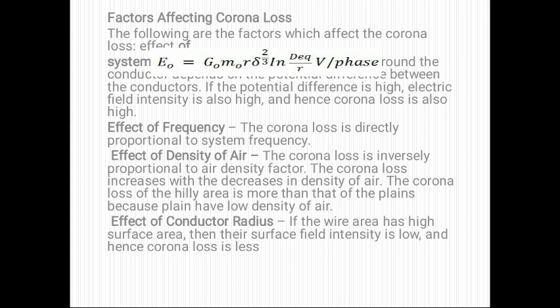Now, factors affecting corona loss: system voltage, effect of frequency, effect of density of air, effect of conductor radius. If the potential difference is higher, electric field intensity is also higher, which causes corona loss. Next, effect of frequency: corona loss is directly proportional to the system frequency as shown in the equation. Next is effect of density of air. Corona loss is inversely proportional to the air density factor. So the corona loss increases with the decrease in density of air. The corona loss of hilly areas is more than that of plain areas because hilly areas have low density of air.